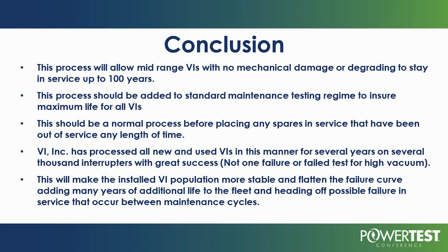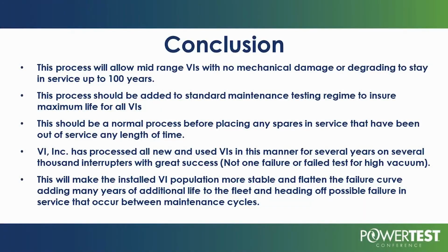We do new interrupters as well as used interrupters, new breakers in the box. I think we've had great success. We've not found any failures or had any failures with any interrupters we've put in the field since we started our conditioning program at VI. We condition every interrupter. We've not had one interrupter come back at loss of vacuum since we started that process. Basically, what we're trying to do is keep the installed base more stable, and keep the installed base in service for a longer length of time. Work with us to help that happen.